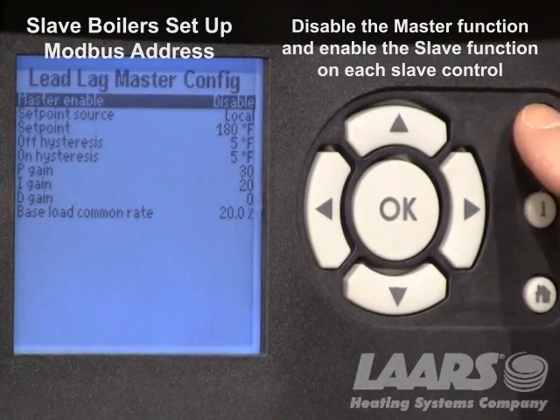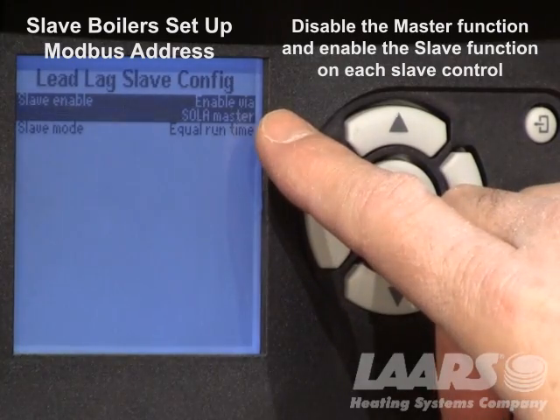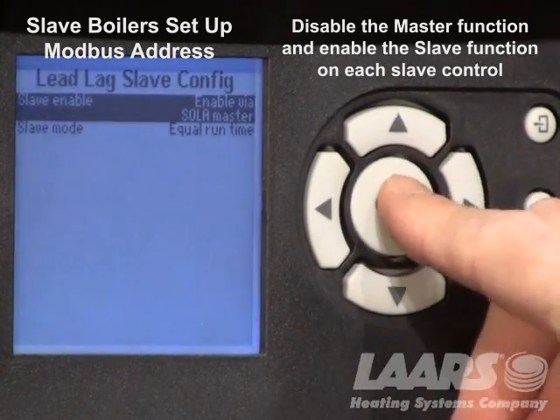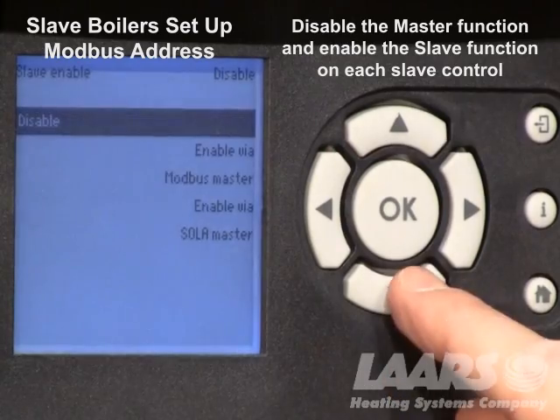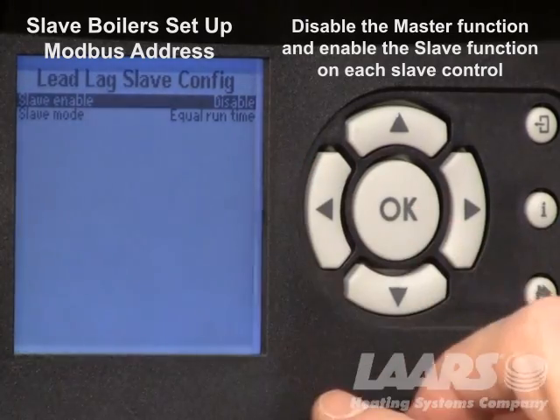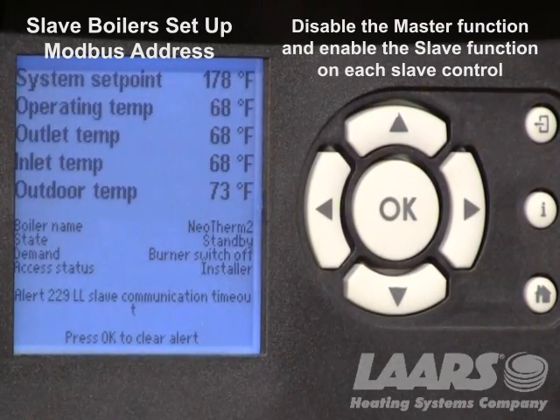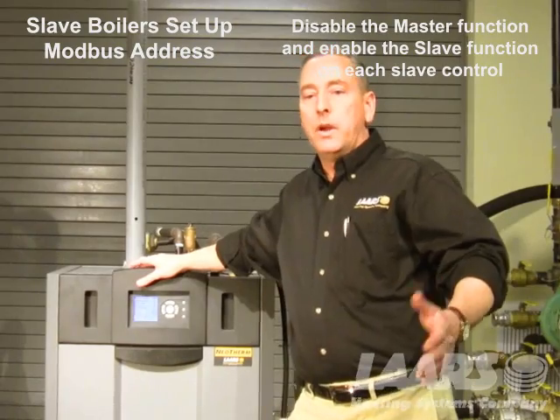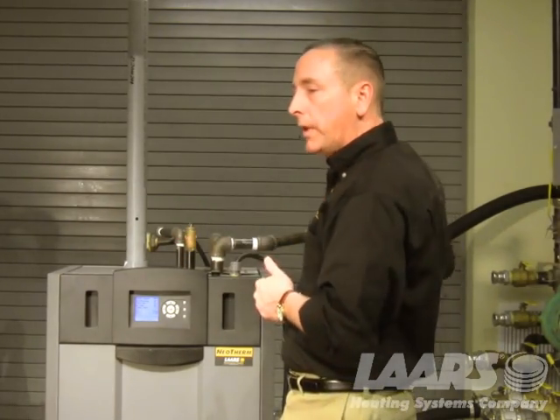Hit the back button and scroll down to lead lag slave configure. Confirm that this is enabled via SOLA master. If it was disabled on the main screen, highlight it, go down, choose enable via SOLA master, press okay, and it will change. Back to the home screen. We've now programmed the master control and the slave controls — we would do that for each slave control. For up to eight boilers in the cascaded system, boilers two through eight will now have these changes.